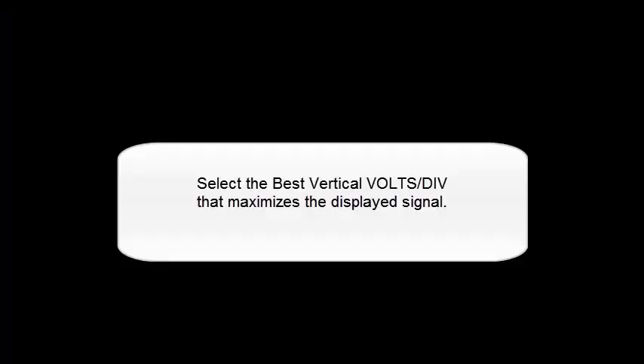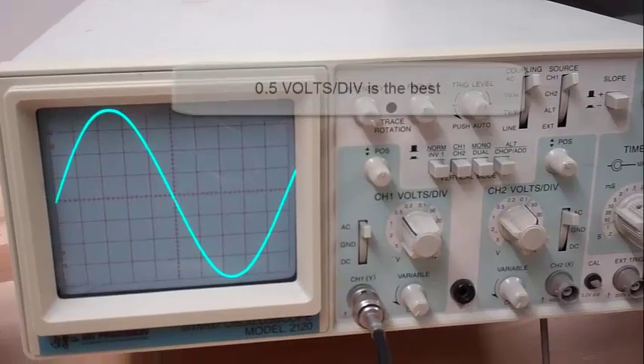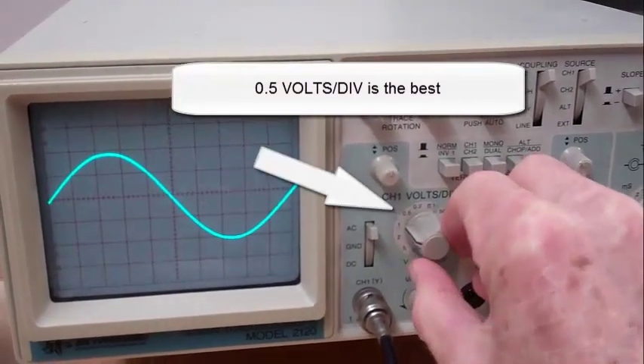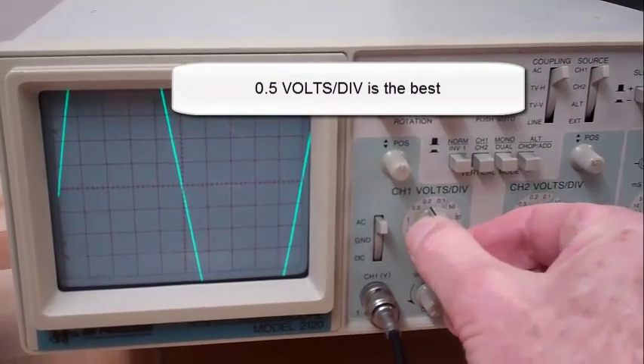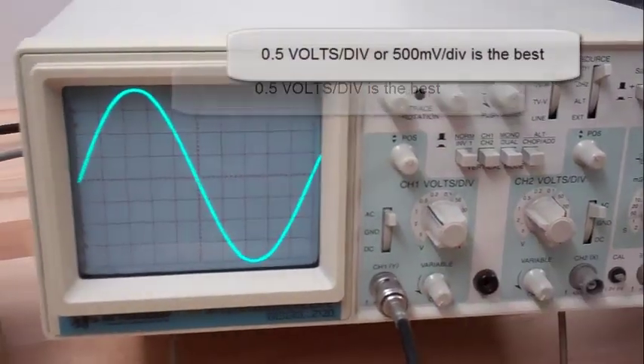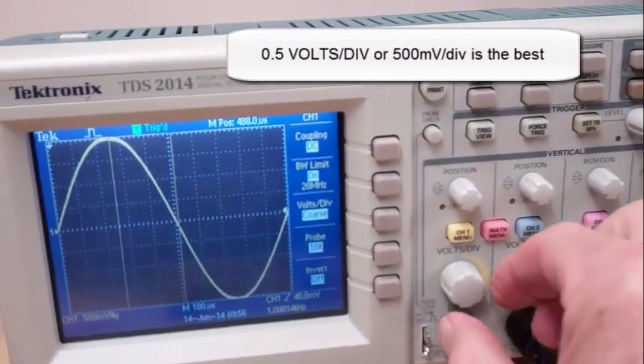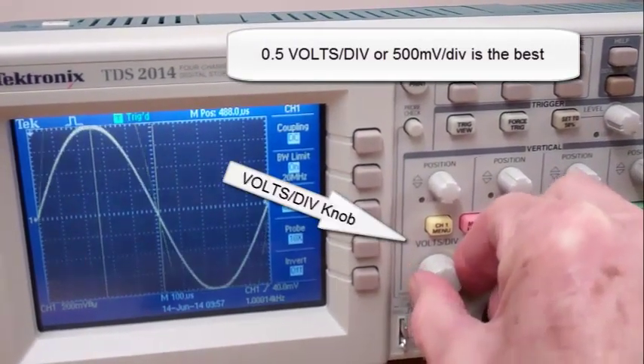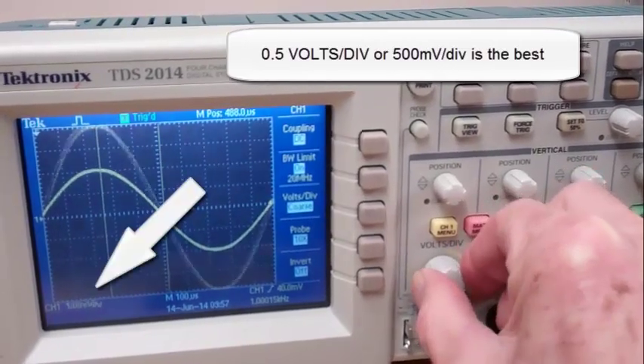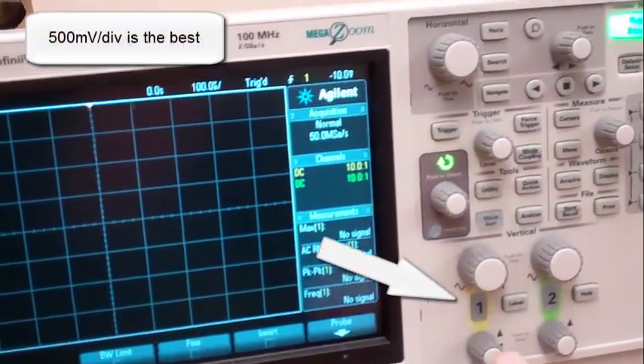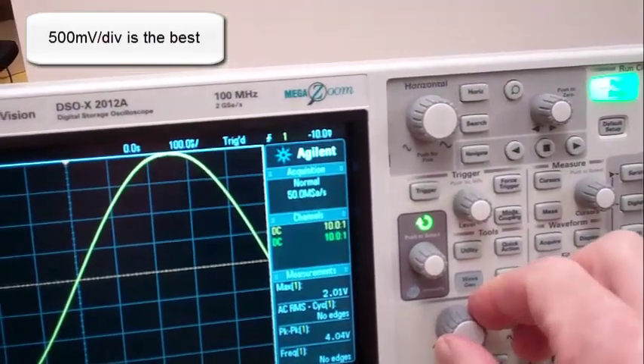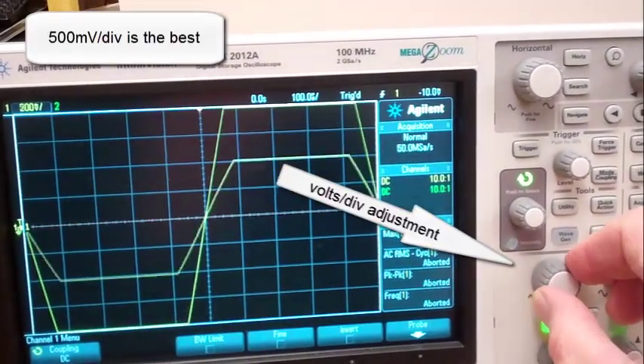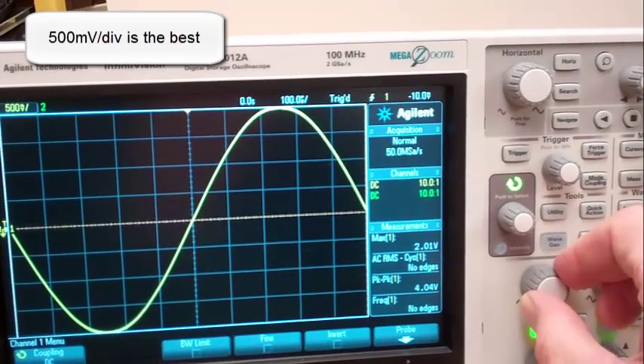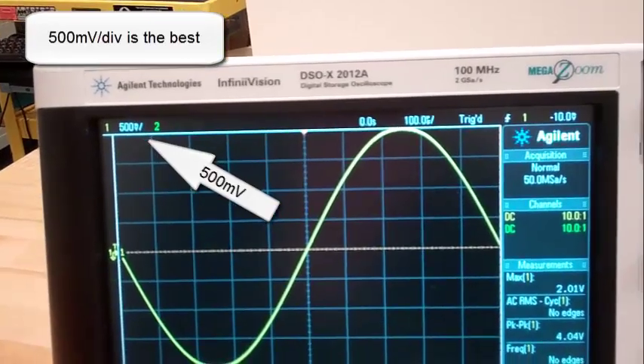Select the best vertical volts per division that maximizes the displayed signal. 0.5 volts per division is best, which is the same as 500 millivolts per division. That's the volts per division knob, showing 500 millivolts. 500 millivolts is best here also, adjusted with the volts per division knob, showing 500 millivolts.